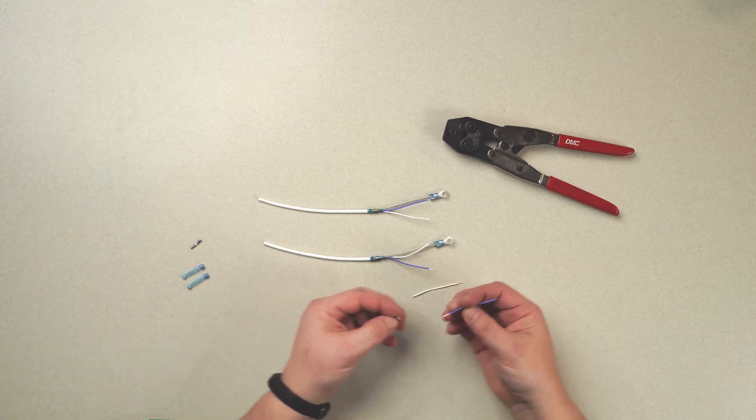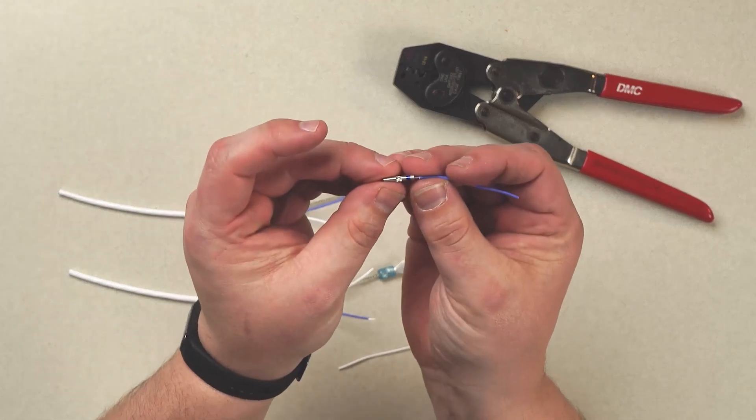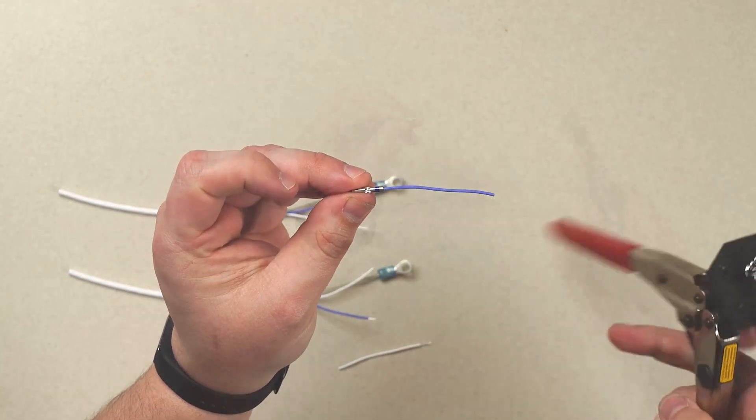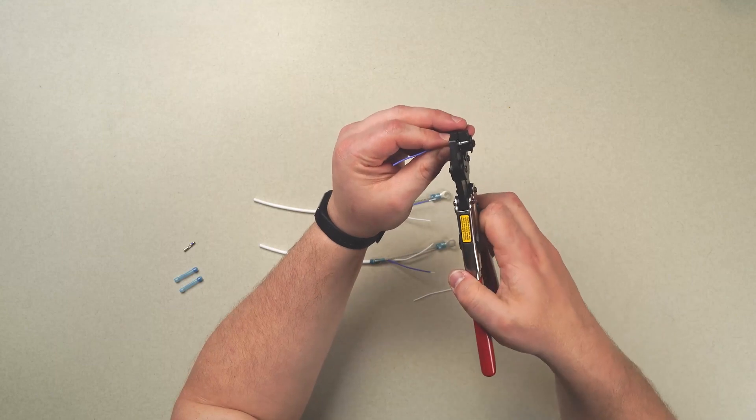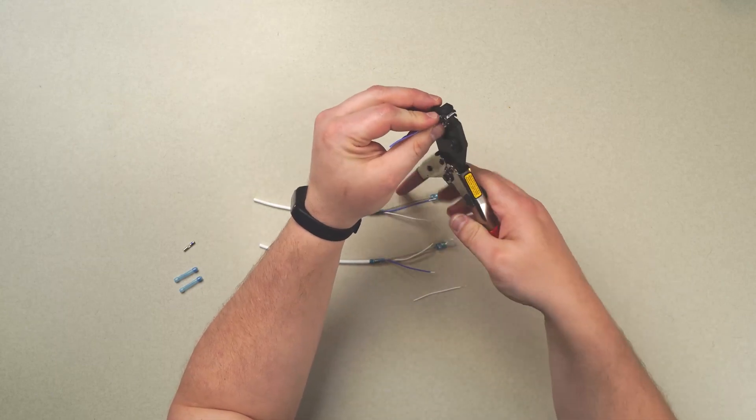Start with our splice and our lead wire, again, making sure that we have full penetration. We can see in the window in the center, the spliced wire is there, and we grab our crimping tool, lining it up with the proper color coding, and then applying the crimp.